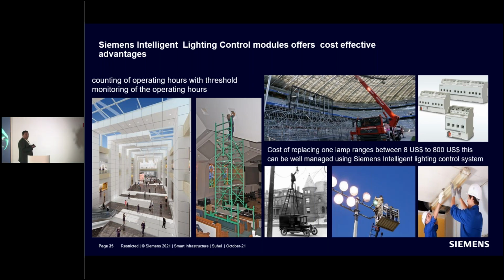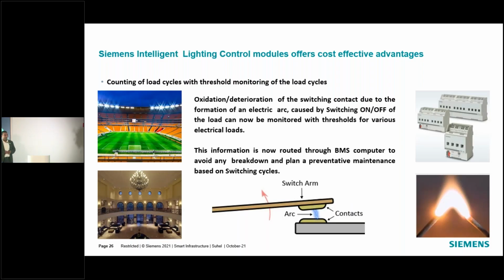You can actually monitor the real-time run hours of the lamp. Also, whatever precaution you take, with the switching module, whenever you open and close the circuit there is always an arc. All the circuit breakers you know—vacuum, air blast, SF6—are all designed to quench this arc, as we all know.